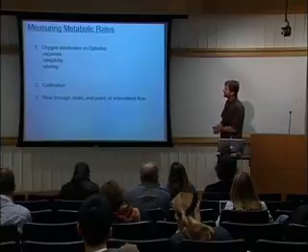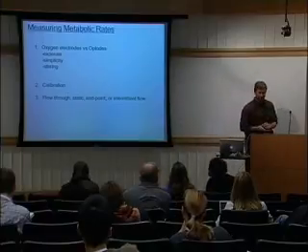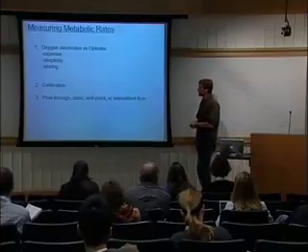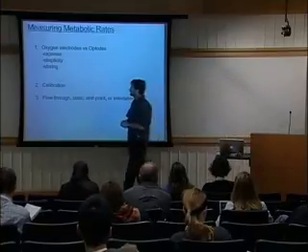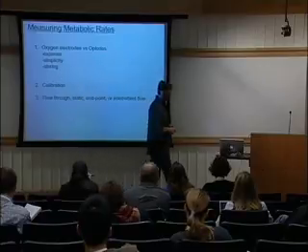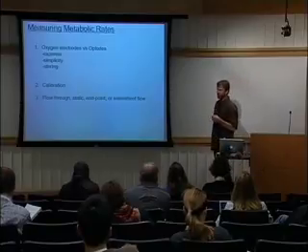So do you want to use electrodes, or what are called optodes, which are optical oxygen sensors? I believe in Portner's chapter in the best practices guide, he leans toward optodes because you reduce the requirement for stirring mostly, and they're less sensitive to temperature. However, you have to stir anyway, and you have to control temperature anyway. So it doesn't really matter in my mind which you're using.